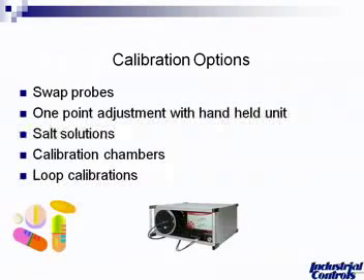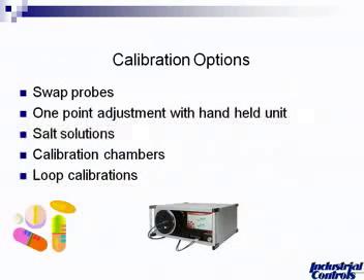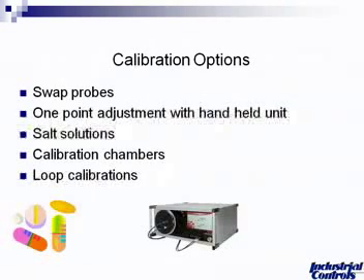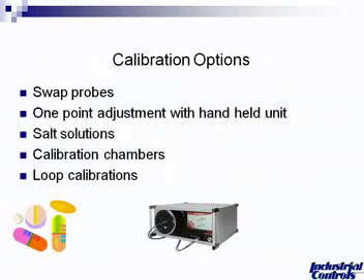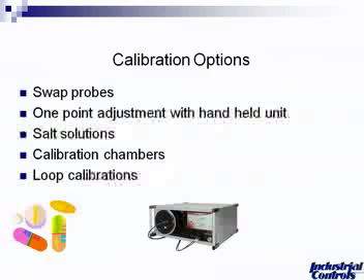There are also calibration chambers — a whole plethora of choices ranging in price from roughly $12,000 all the way up to $50,000 depending on what you're trying to do. There are flight-and-float types and two-pressure, two-temperature systems. If possible, ask the manufacturer for a stability analysis, which gives you information on how stable the inside of the chamber is — they've tested every inch of that chamber, and you know roughly what you're getting for accuracy throughout the entire chamber, your speeds of response and so on. Cheaper isn't always better.